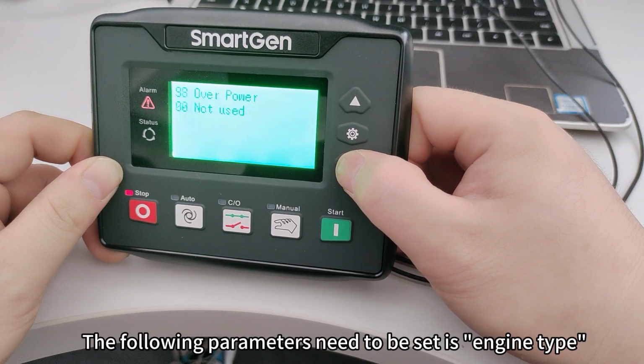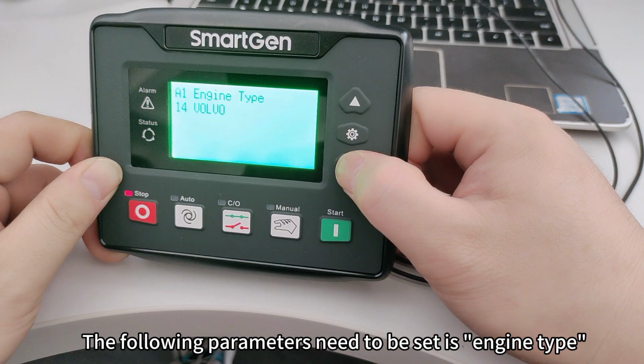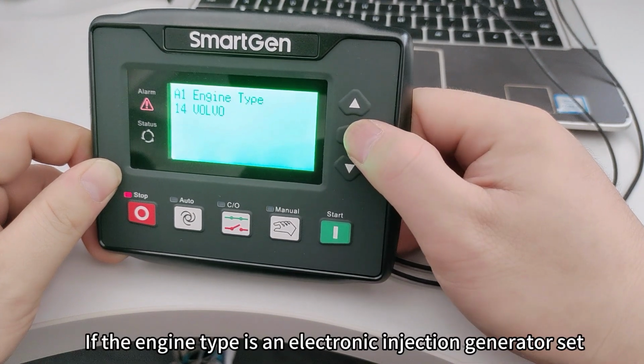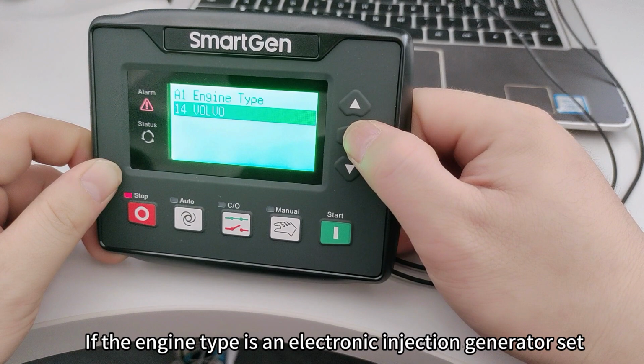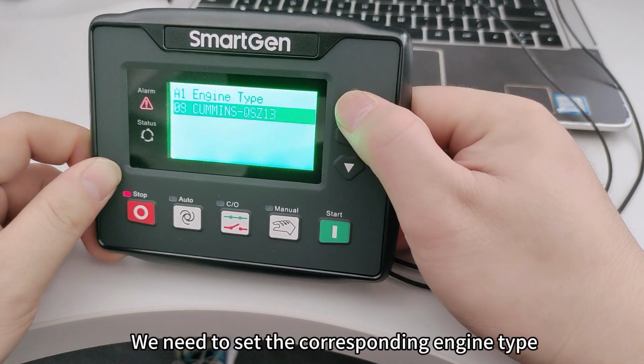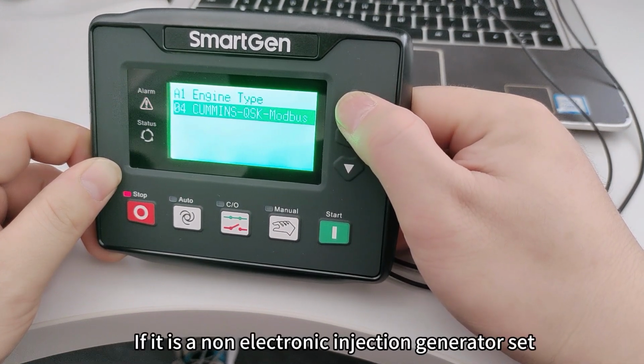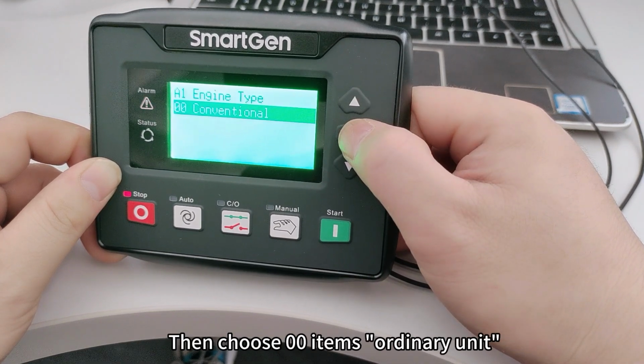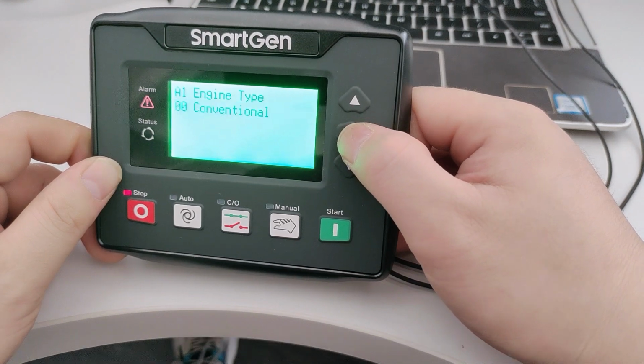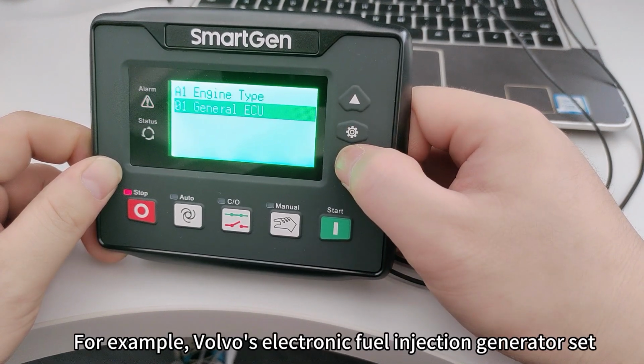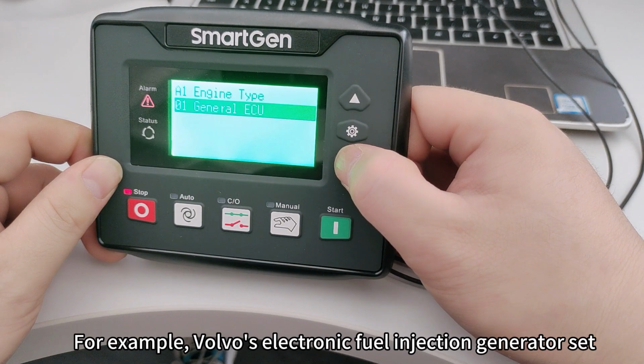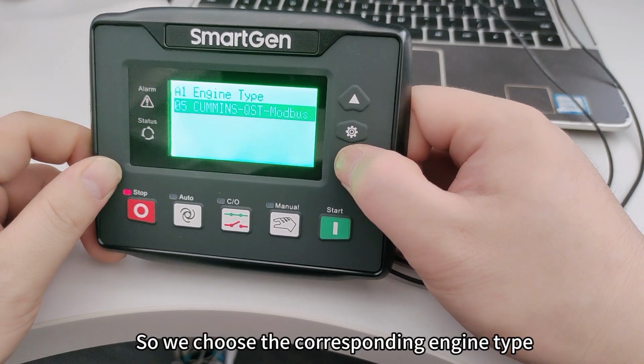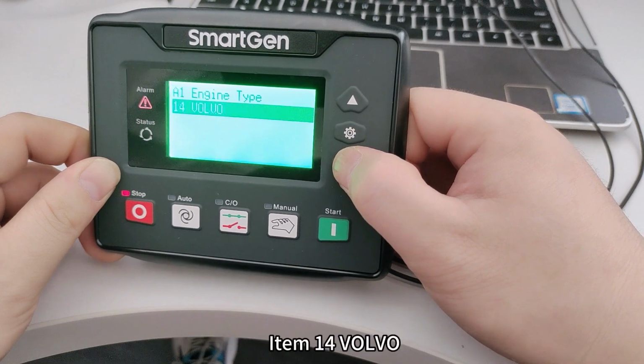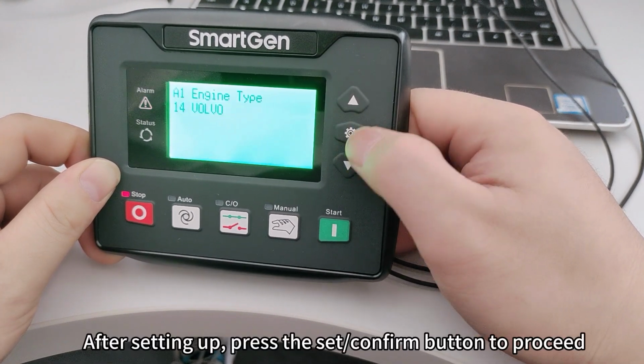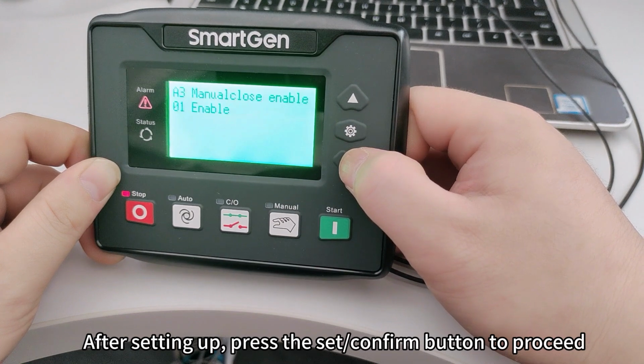The following parameter that needs to be set is the engine type. If the engine is an electronic injection generator set, we need to set the corresponding engine type. If it is a non-electronic injection generator set, then choose item 00, ordinary unit. For example, for a Volvo electronic fuel injection generator set, we choose the corresponding engine type, item 14 Volvo. After setting up, press the Set Confirm button to proceed.